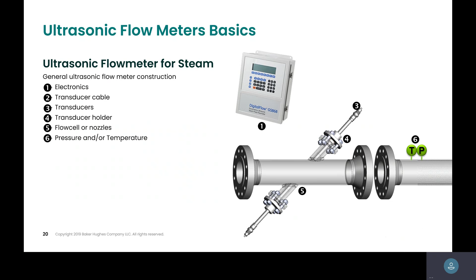The most common way, shown in this picture, has the piezoelectric crystal at the end of the transducer - probably the most common design you'll use. You can see it's really in the nozzle, shooting from that edge and sending the signal. For high temperature systems, the transducer is actually located here and goes through what's called a buffer rod.